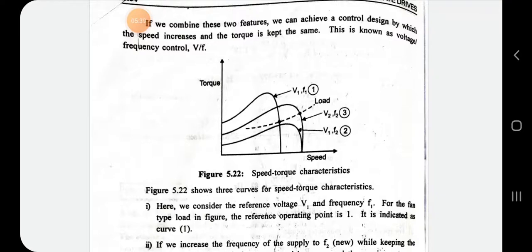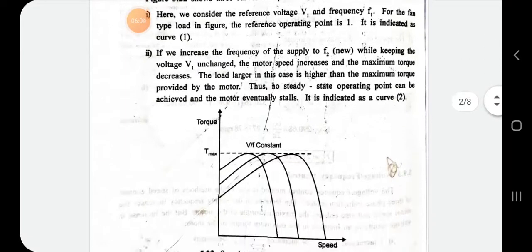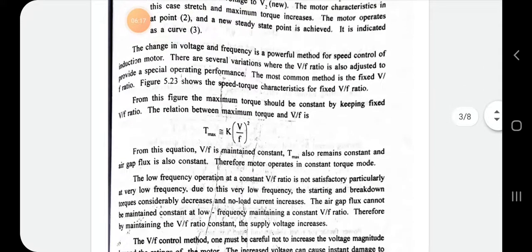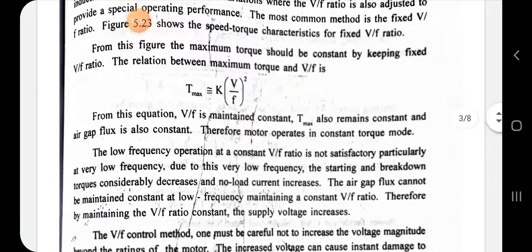By varying the V/f ratio, when we change the speed of the induction motor, simultaneously the V/f ratio is fixed — corresponding voltage and frequency values are adjusted together. By fixing the V/f ratio, speed control is achieved. The maximum torque is given by T_max = k·(V/f)², so torque remains constant and air gap flux also remains constant, allowing the motor to operate in a constant torque mode.